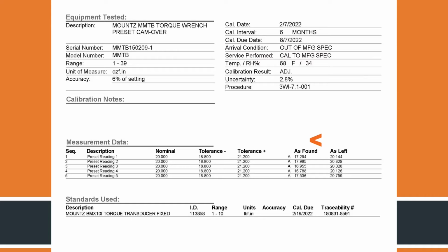Now you can see with this tool, it was found slightly below the acceptable tolerance for this tool. So these are right around 17 or so inch ounces, and our low tolerance on here is 18.8. And so this is a scenario where maybe a torque verification process may have caught this as found date earlier than before it was sent out for calibration.